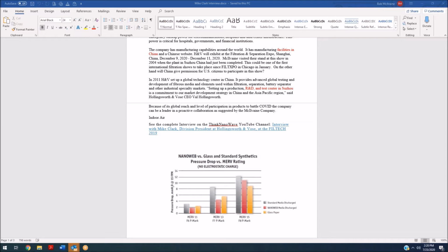Of course, it's going to be constrained by what the footprint is and what the form factor of the filter can be. Certainly, we really like the nanoweb technology for its baseline mechanical filtration. Of course, it can be boosted with an electrostatic charge to make it even higher. That's our favorite solution, but of course we have the historical mechanical means like glass filter media or even pleatable synthetics type media that can also do that. The filtration technology is there.